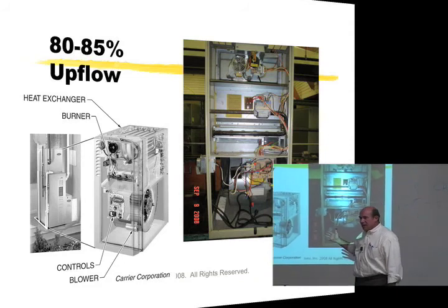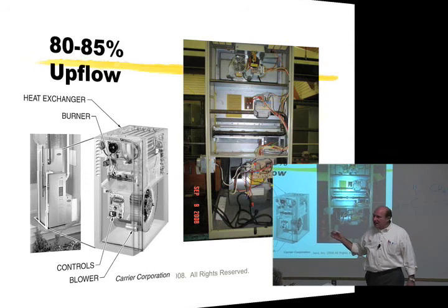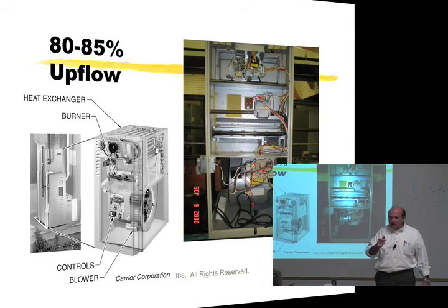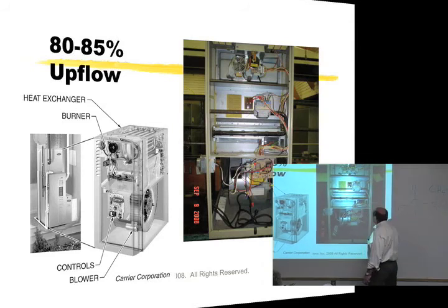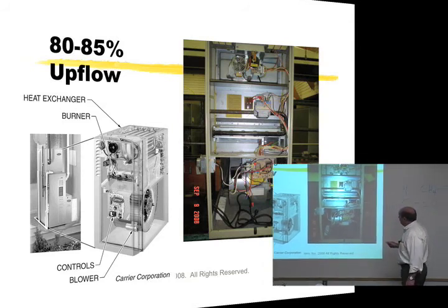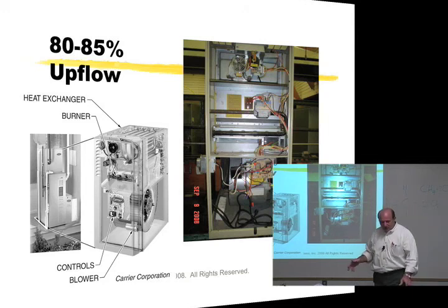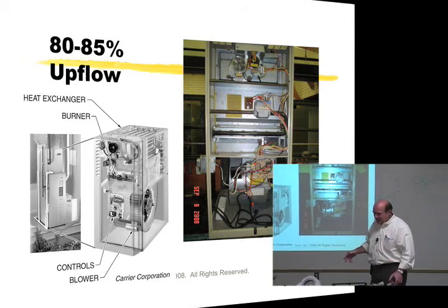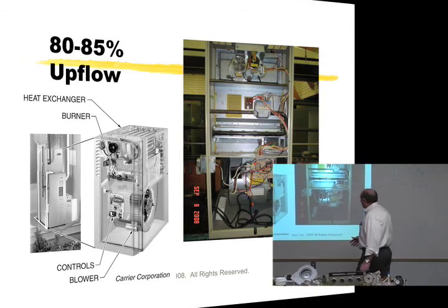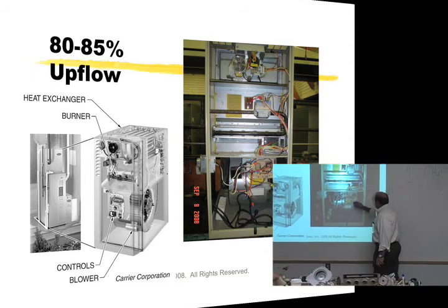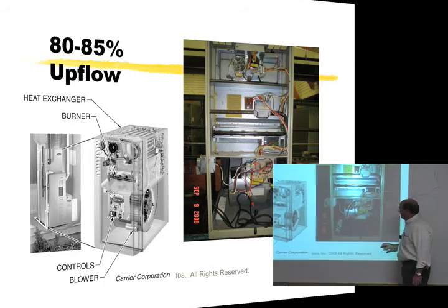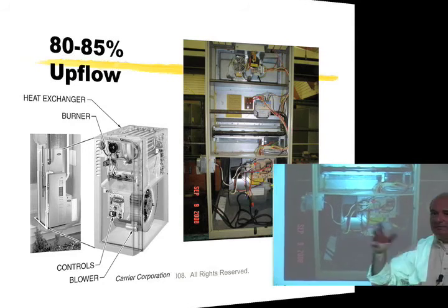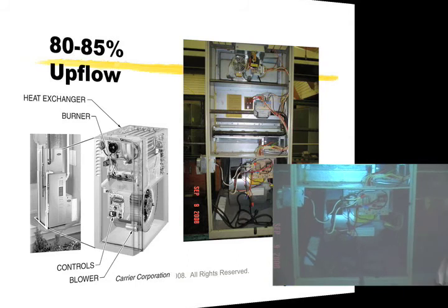In case the products of combustion, the natural gas that's being fired, if it rolls out of that burner compartment, or if it spills out of the burner compartment for some reason, it'll hit that switch and it'll shut down the blower as well, so we don't get a fire or a severe upset condition. So we got a couple of other items on these newer furnaces. We have the snap disc limits. We have the pressure control, the fan assist. We also have an integrated circuit board here that does all of the, it's a computer that runs our furnace for us.